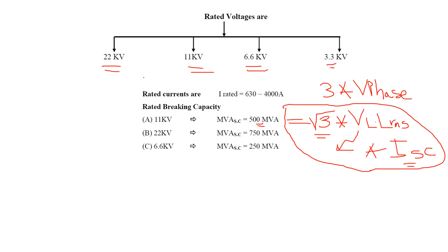These breaking capacity values depend on the power grid. According to your specific grid, you will know the MVA short circuit value for each voltage level. You identify the maximum short circuit current, and from that you determine the required MVA. These values are standardized per power grid — not worldwide, but specific to each grid.